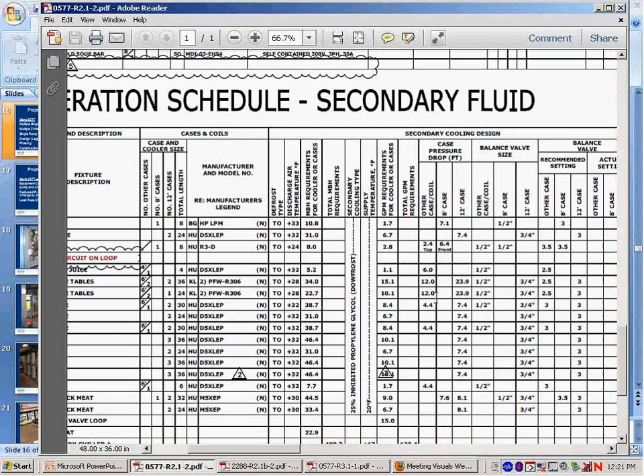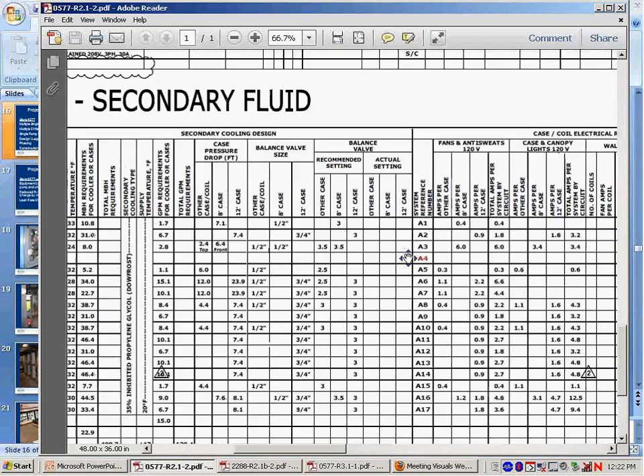We looked at what we were able to determine as pressure drops for each lineup, and we were also able to suggest a balance valve setting. These are definitely recommended settings, not default settings - some others can speak to that a little bit - but this was a good starting point. Here are the compressors, which were all single systems basically tied together.